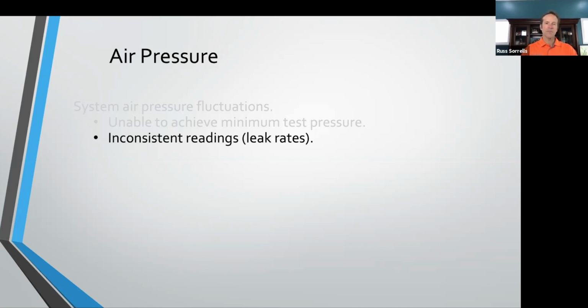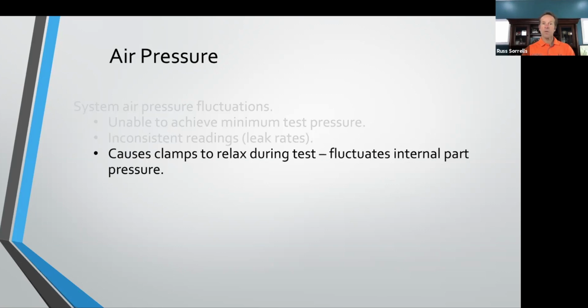So inconsistent test pressure readings result in inconsistent leak rates, because obviously we're pressurizing a part. When we do pressure decay leak testing, specifically, we are measuring the pressure loss over time. So we pressurize the part, and any pressure change, pressure fluctuation is going to cause our results to be inconsistent. So air pressure. We talked a little bit about this last week as well.